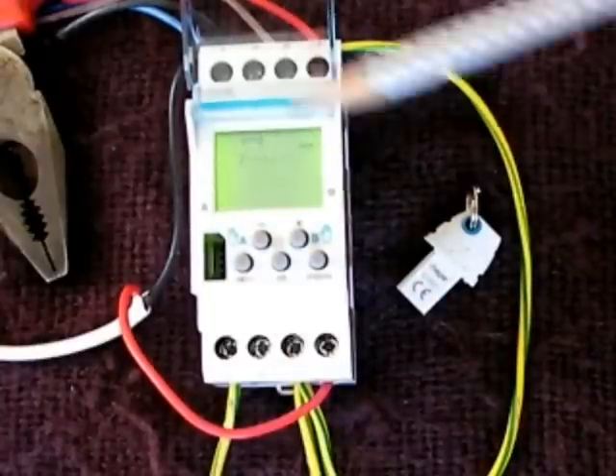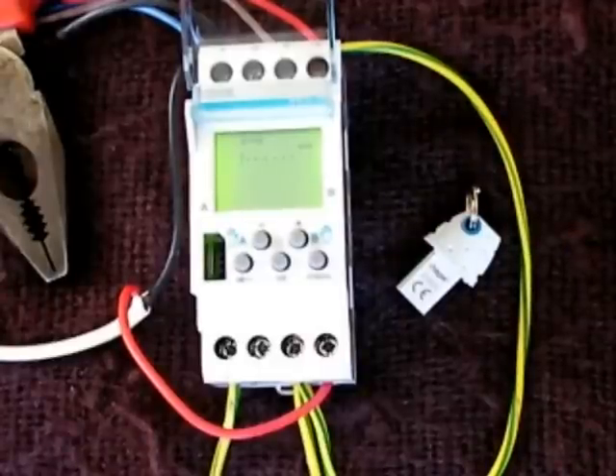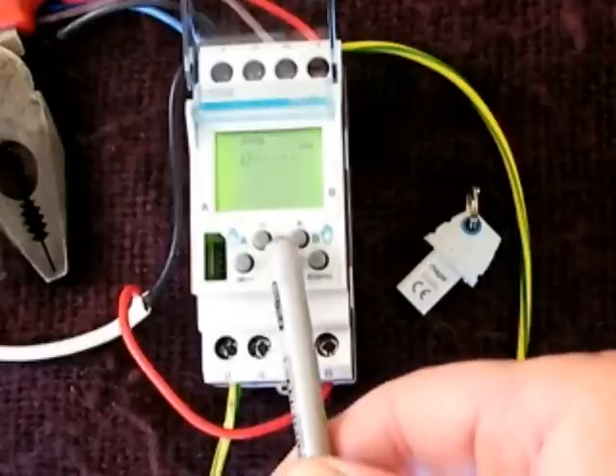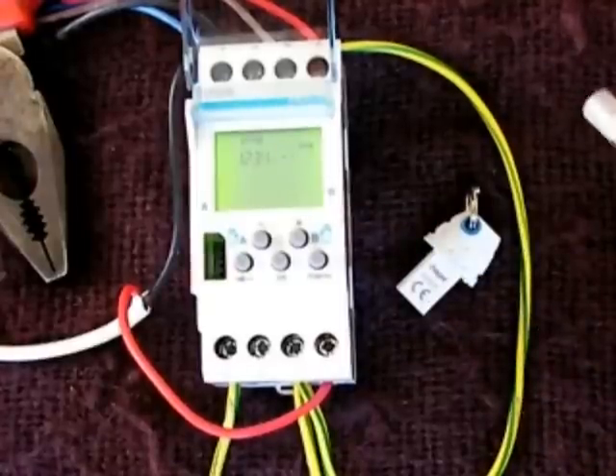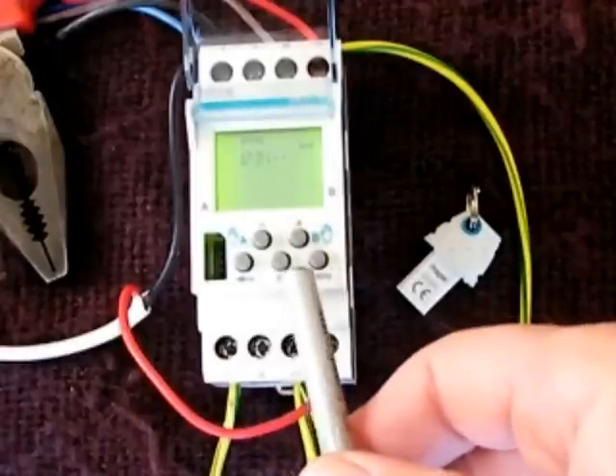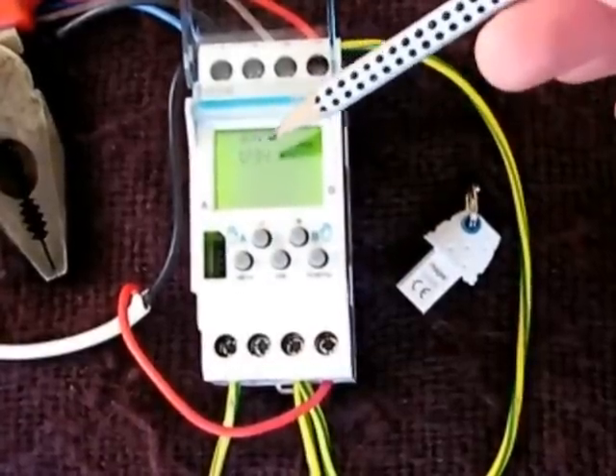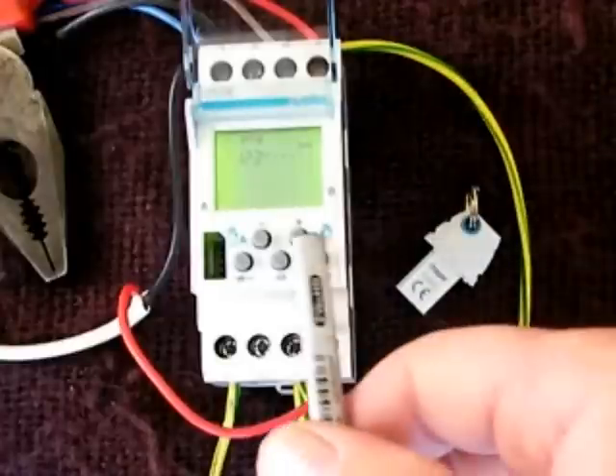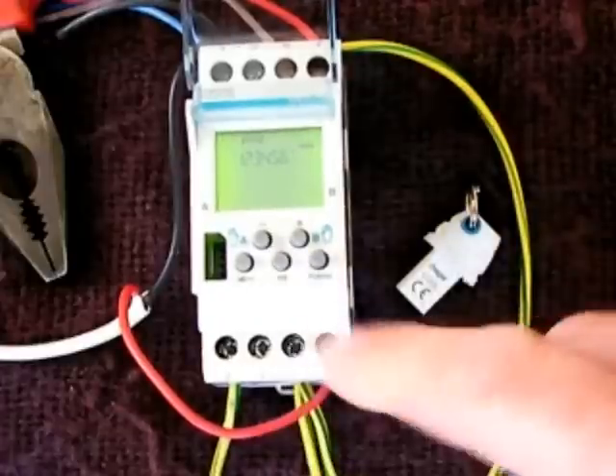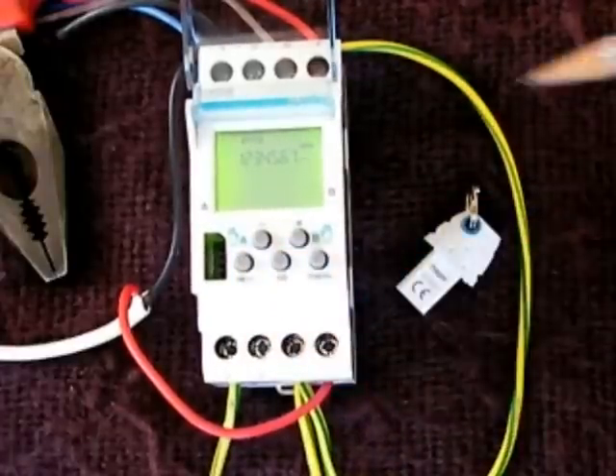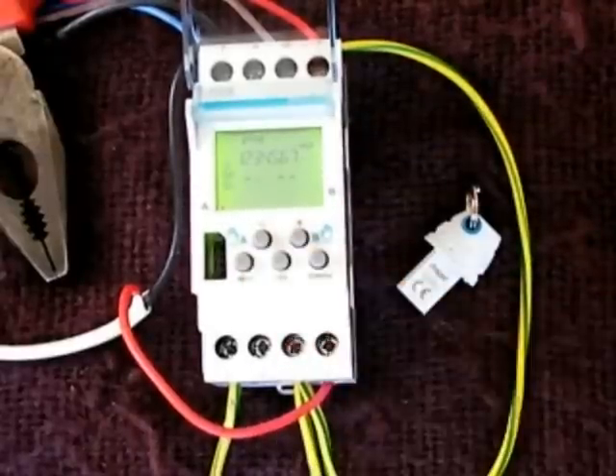We're going to go A, press OK, and you see numbers come up. The numeral one means Monday, the numeral two will mean Tuesday, three Wednesday, four Thursday and so on right throughout the week. The particular setup I'm setting here is seven days - I want these car park lights to come on for seven days at a particular time and go off at a particular time. But if you just want it Monday, Tuesday, Wednesday and skip Thursday, well you would leave the four blank.